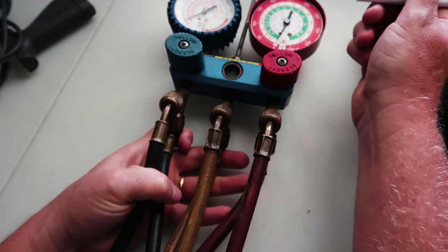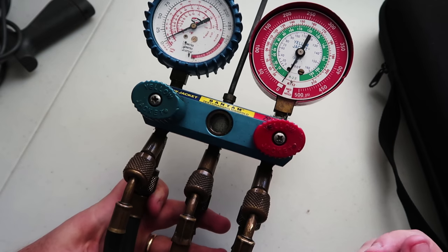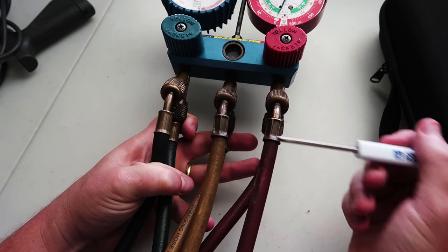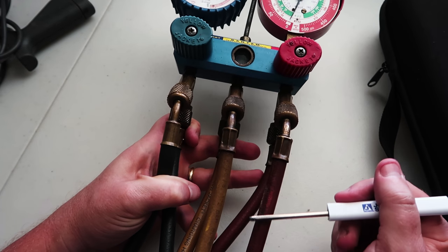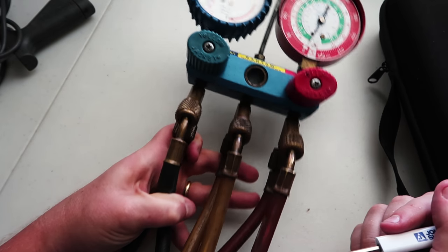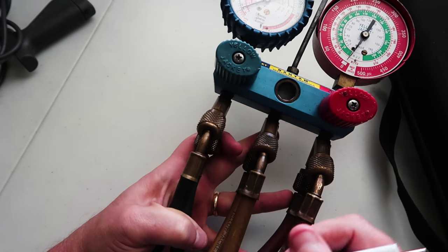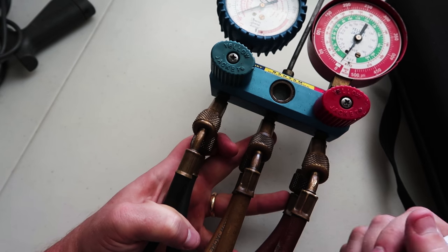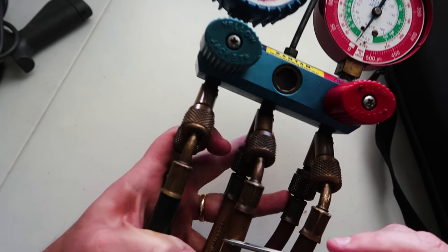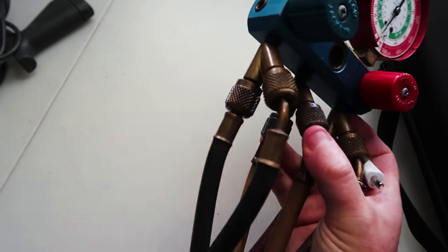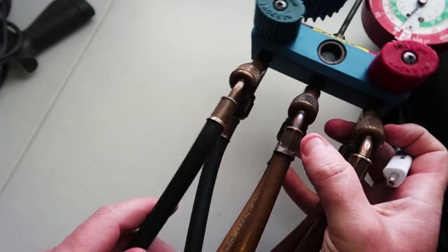This is what we call our high-side gauge, our high-pressure gauge. The hose is red for that. Now again, does the color of the hose matter? Not really, but we use these standardized colors, so that way we don't accidentally get them on the wrong side. The center port here is for our charging and recovery, and we use yellow for that, and then our left side is our low side, our low-pressure side, and it feeds up into this gauge right here.